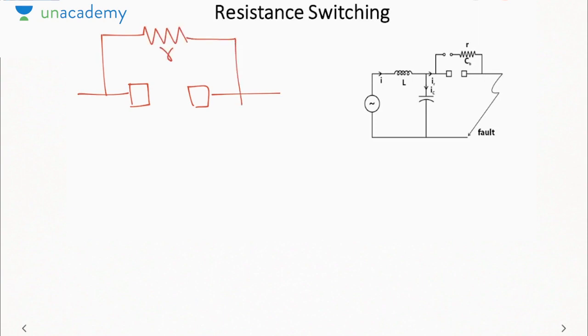Now the problem with connecting a resistance like this is, whenever the circuit breaker opens the circuit after the final extinction of the arc, after the arc has gone away, the plates will behave as an open circuit. Then the current will flow through the resistance. That means after the final extinction of the arc, I have to take care that I disconnect the resistance. That means in series with the resistance we need a switch which will disconnect the resistance as soon as the arc is extinct. Okay, so that is why in series with the resistance we use a sphere gap.